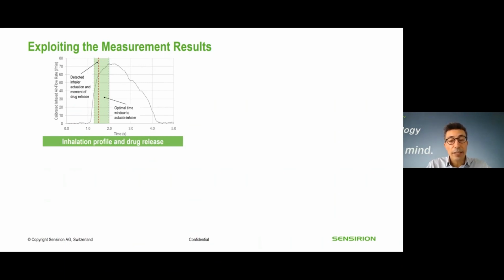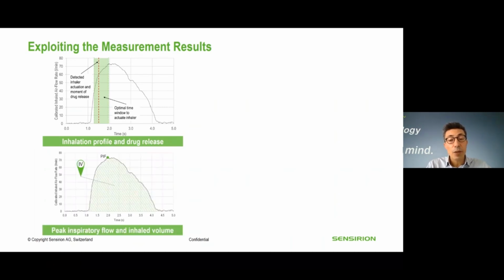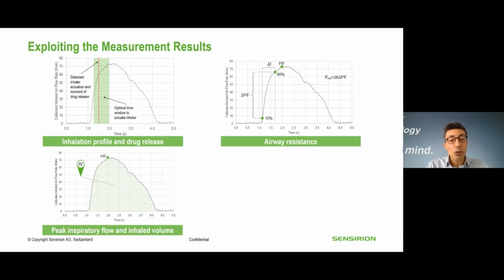The inhalation profile gives an indication whether the patient inhaled slow and deep enough. In the next curve, we identify the peak inspiratory flow rate. The integration of the flow rate over time gives the total inhaled volume. In the next curve, a calculation of the airway resistance is performed. The airway resistance is defined by the ratio of the time needed to increase the flow rate from 10 to 90% of the peak inspiratory flow rate, divided by the value of the said peak inspiratory flow rate.